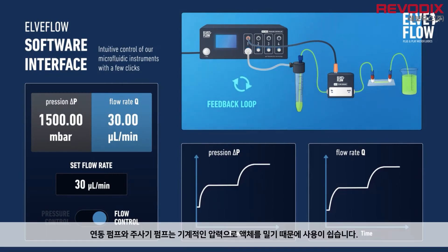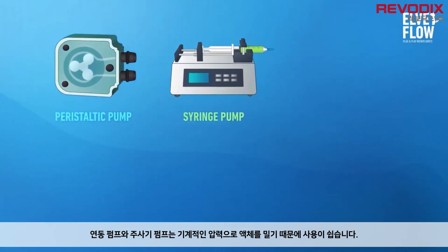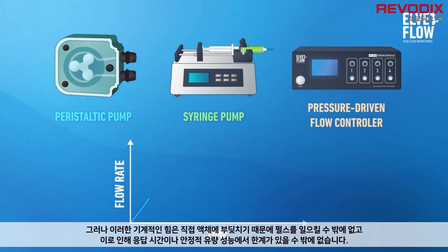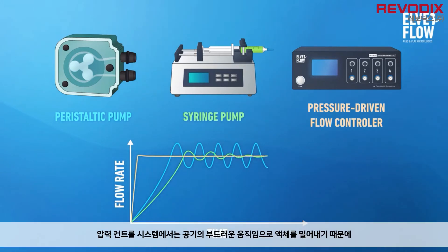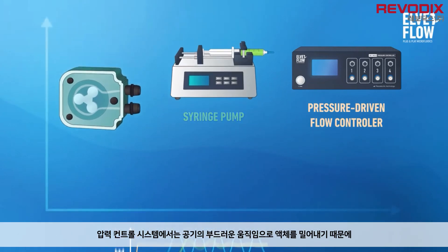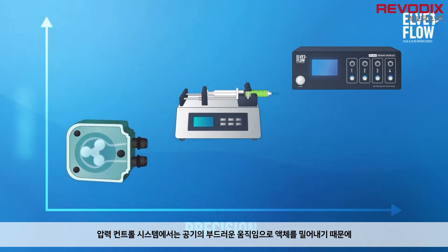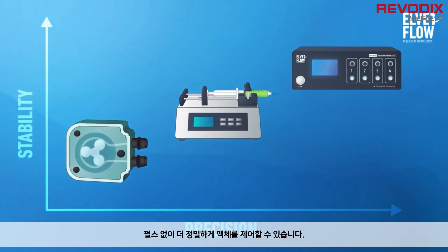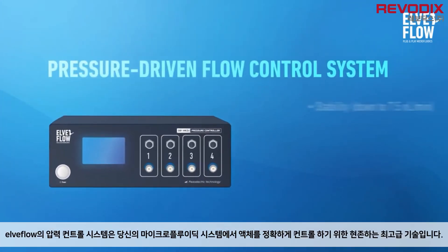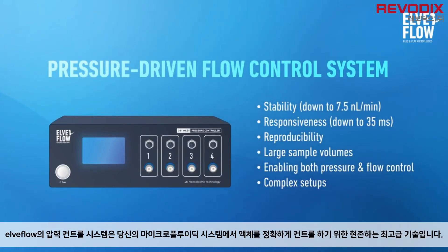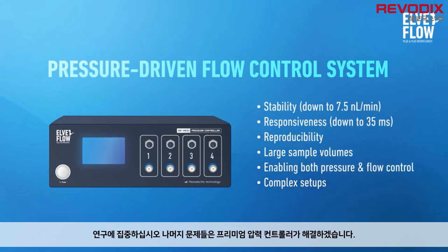Both peristaltic and syringe pumps are easy to use — they push liquids by a mechanical action. Yet this mechanical movement leads to bumps and pulses, limiting performances in terms of response time and flow stability. In a pressure-driven flow control system, the liquid is pushed by a gas in a smoother action, leading to a pulseless flow and a higher flow control accuracy. Pressure-driven flow controlled microfluidics is the premium solution to accurately control fluids in your microfluidic setup.